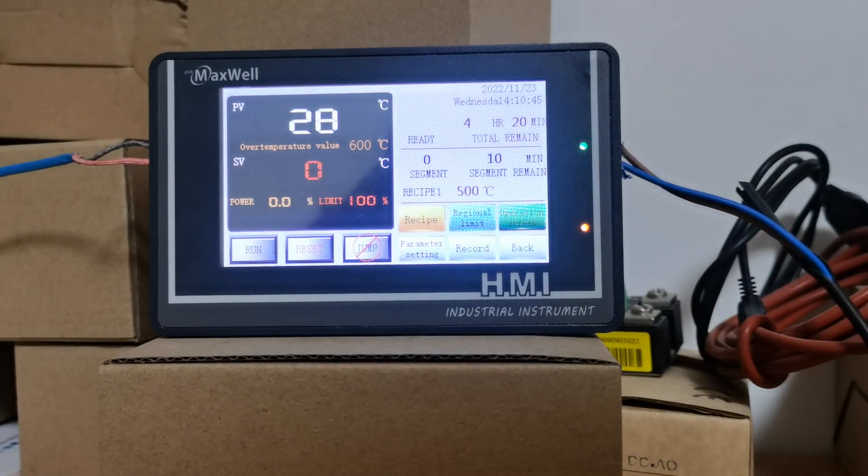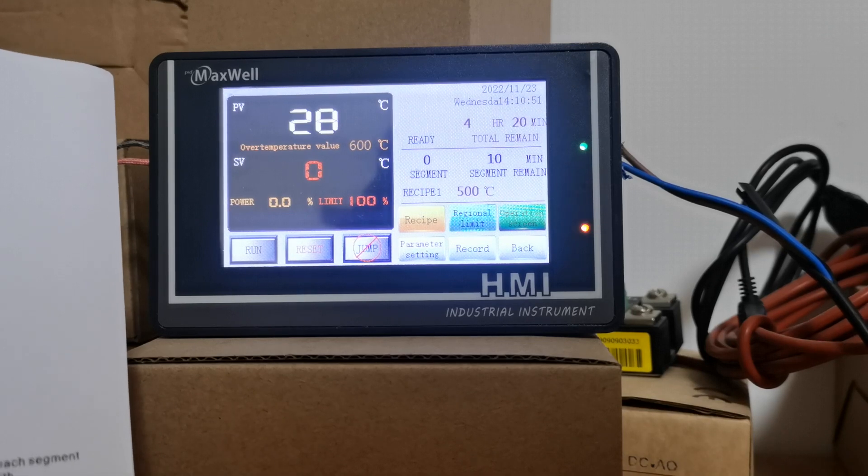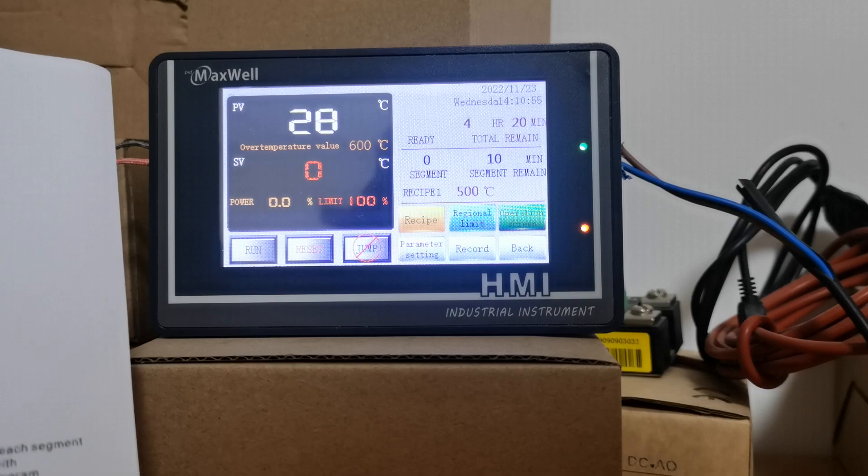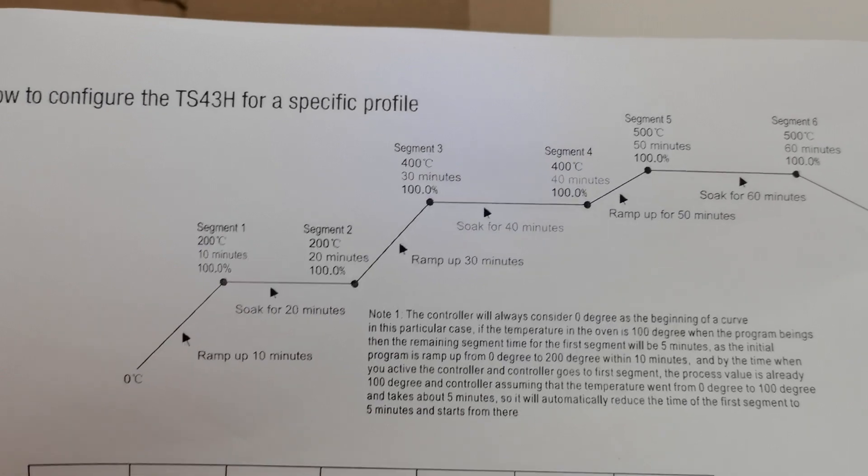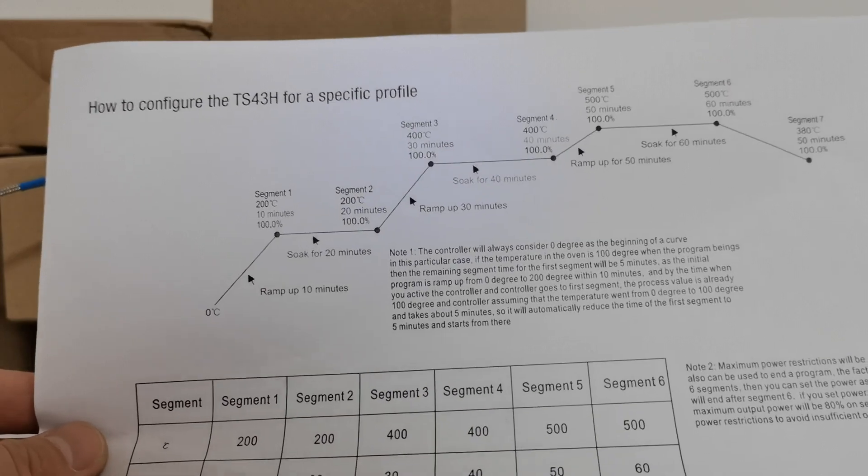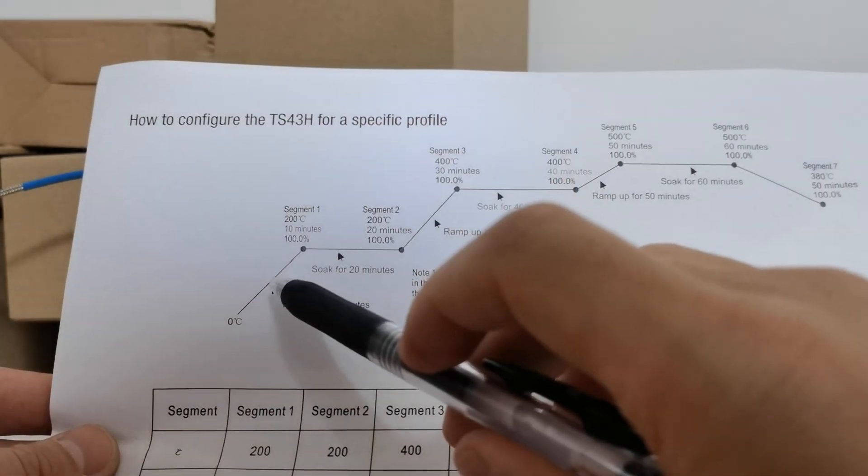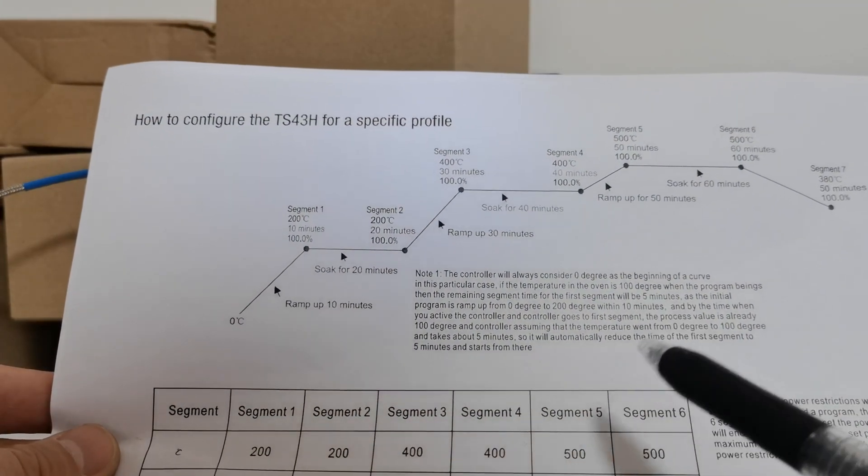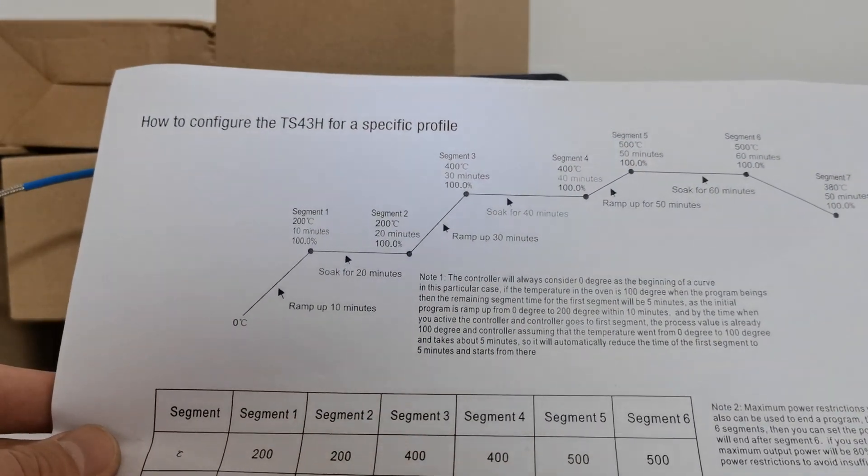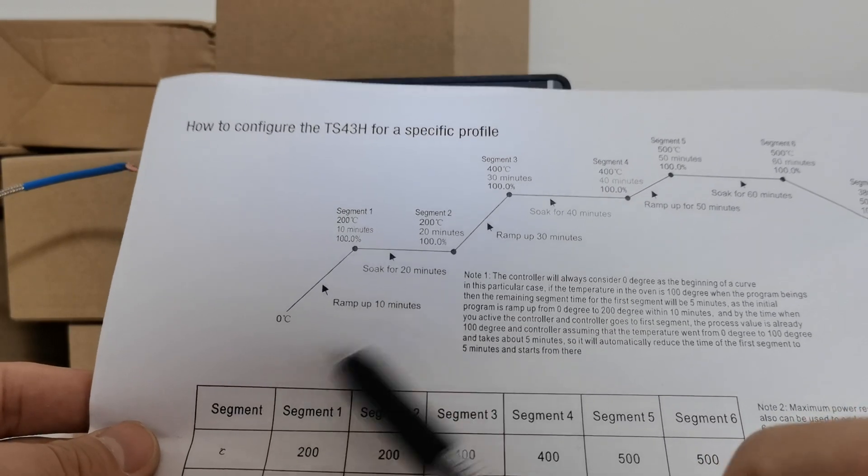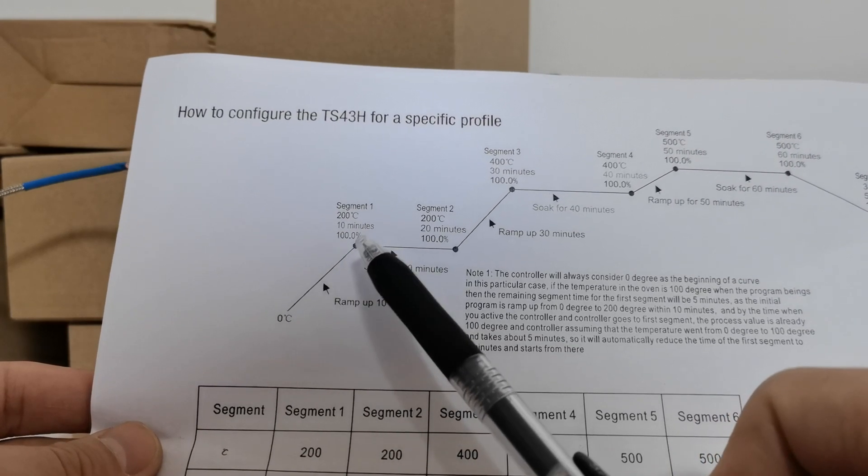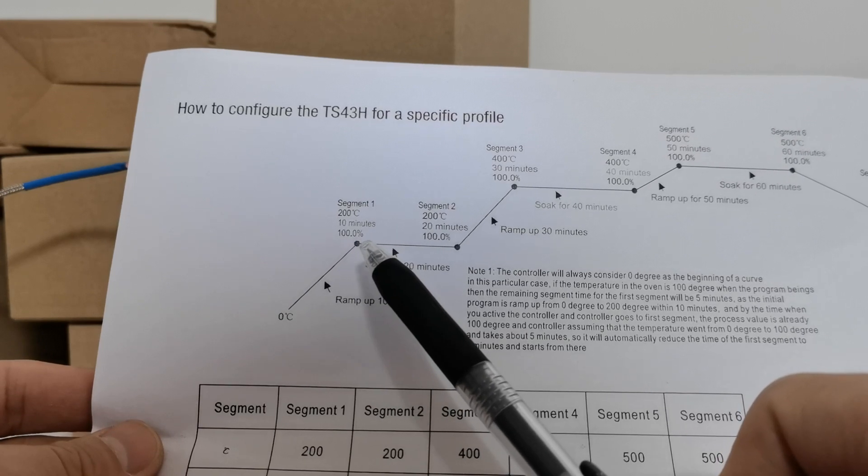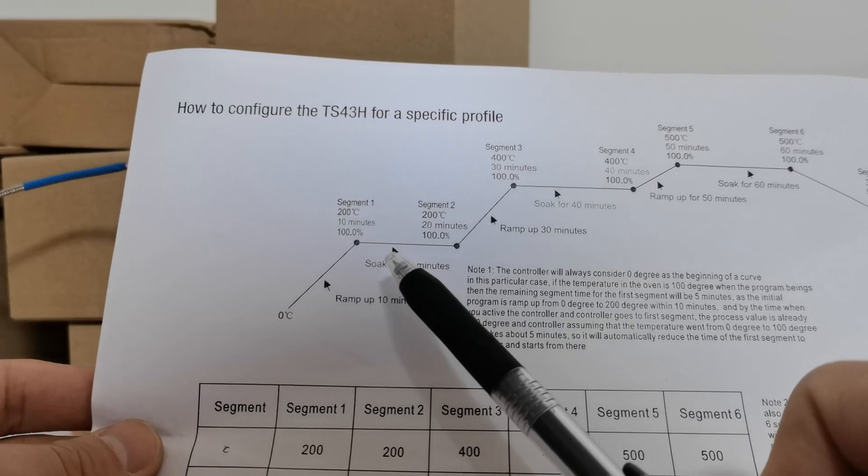Now here comes the most important part: how to program the controller to work to a specific profile. I have the profile printed on the paper - one, two, three, four, five, six, seven. There are a total of seven segments within this profile. The first segment takes 10 minutes from zero degrees to 200 degrees, and the second segment is a 20-minute soaking process.